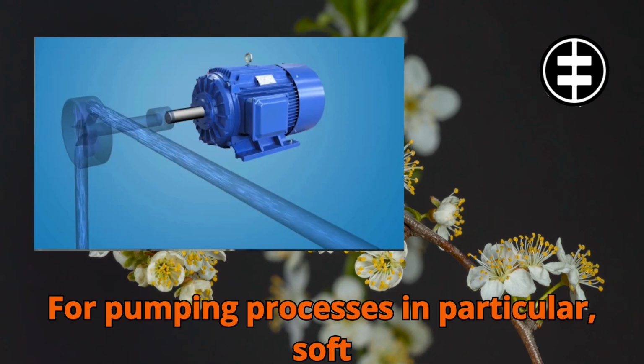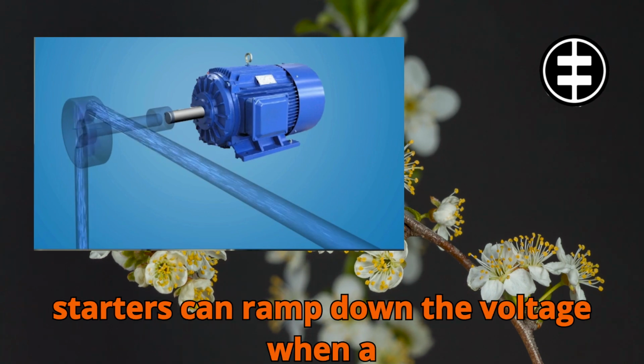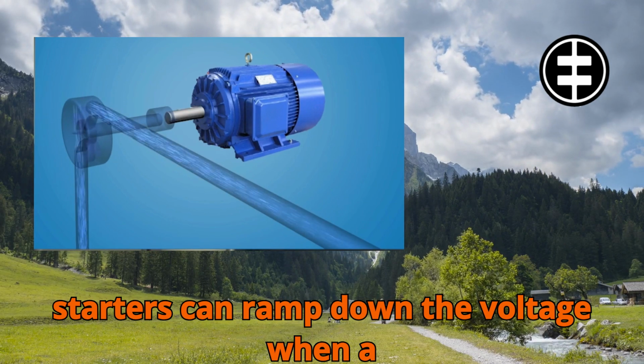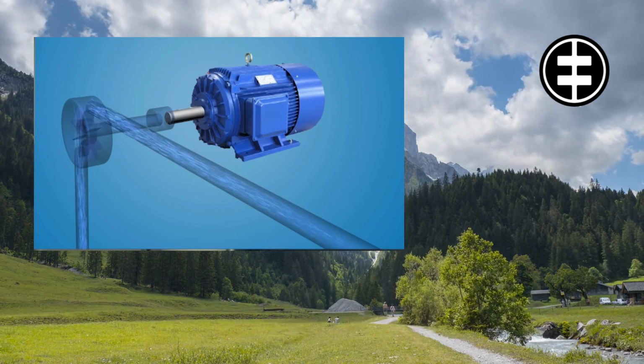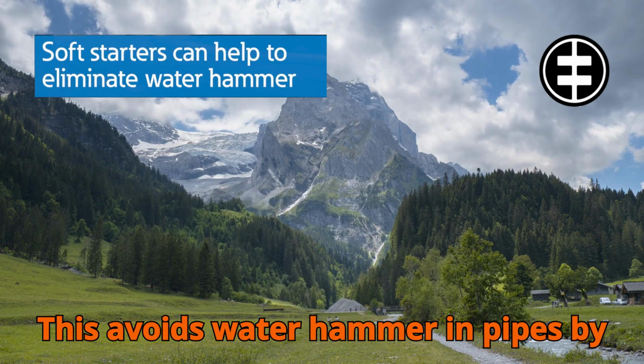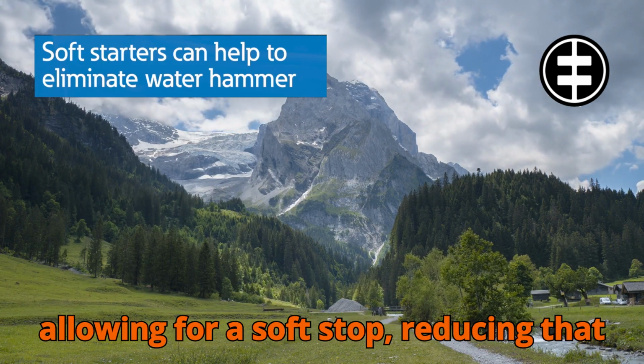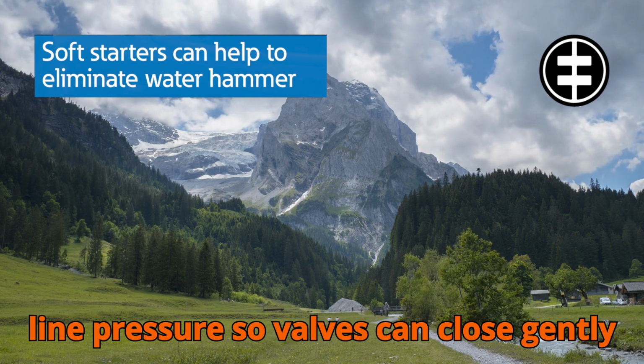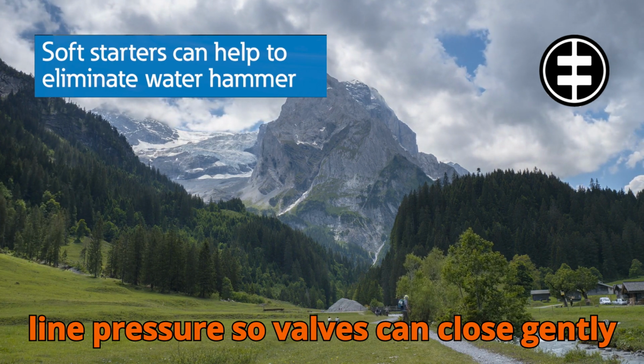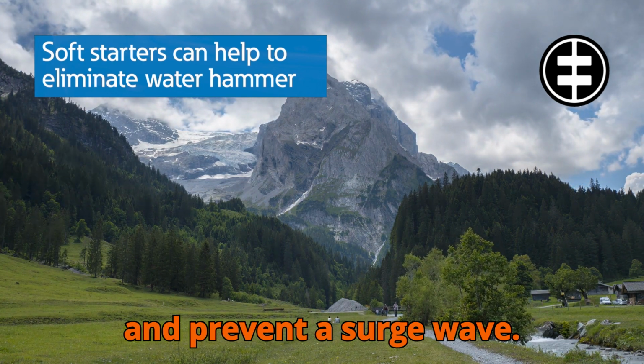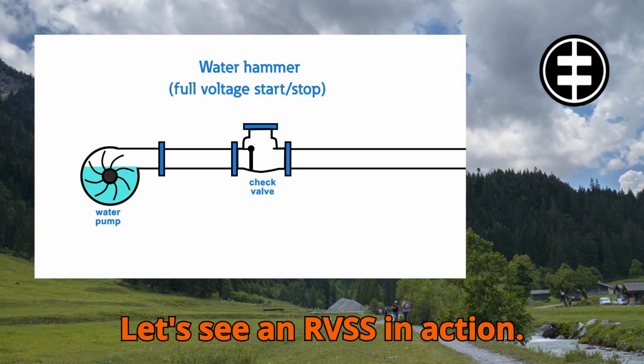For pumping processes in particular, soft starters can ramp down the voltage when a stop command is given. This avoids water hammer in pipes by allowing for a soft stop, reducing that line pressure so valves can close gently and prevent a surge wave. Let's see an RVSS in action.